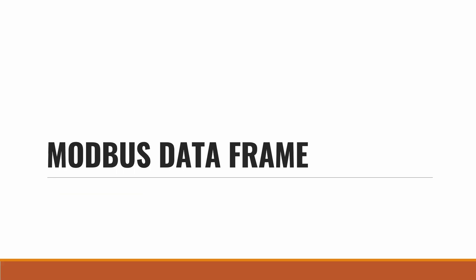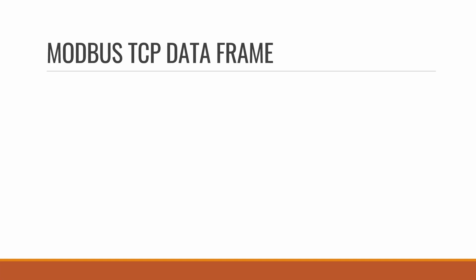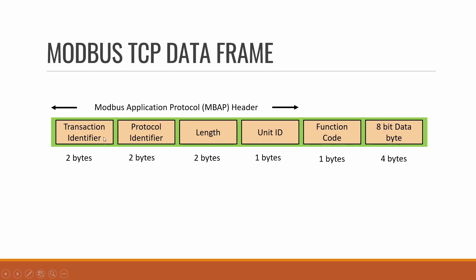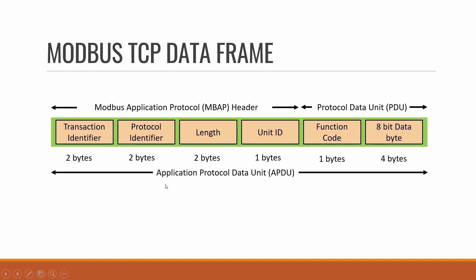Next we will discuss the Modbus data frame. The Modbus TCP data frame consists of: a transaction identifier (2 bytes), a protocol identifier (2 bytes), a length field (2 bytes), a unit ID (1 byte), a function code (1 byte), and 8-bit data (4 bytes). The transaction identifier, protocol identifier, length, and unit ID together form the Modbus Application Protocol Header (MBAP header). The remaining portion — function code and data — is called the Protocol Data Unit (PDU). The entire data frame is called the Application Protocol Data Unit or APDU.